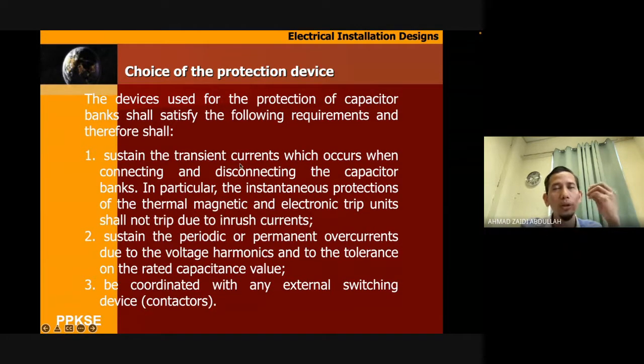And firstly, you need to remember that it is related to the transient. A transient is a very high rush signal or peak in a short time. So we need to control it. In particular, the instantaneous protection of the thermomagnetic and electronic trip shall not trip due to inrush current. And then number 2, we need to sustain the periodic or permanent overcurrent due to voltage harmonics and to the tolerance of the rated capacitance value. And lastly, to coordinate with any external switching.